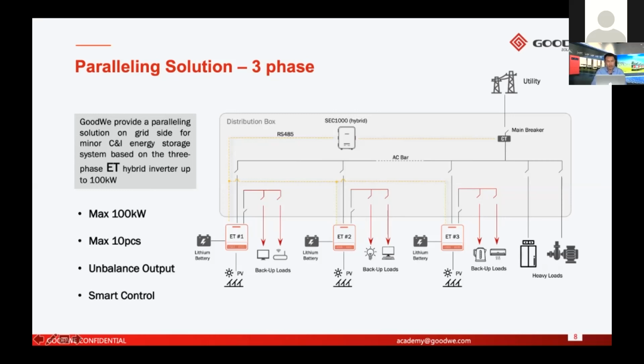For paralleling systems on the ET series, you can parallel a maximum of 10 units. It means the paralleling system can range from 15 kilowatts to a maximum of 100 kilowatts. For the ET series, we have 5, 8, and 10 kilowatt models. If you want to build a paralleling system, you can parallel all 10 kilowatt units, or mix 5, 8, and 10 kilowatt units together. ET paralleling systems can also support unbalanced outputs. I will talk about the unbalanced output function in detail on the following pages.